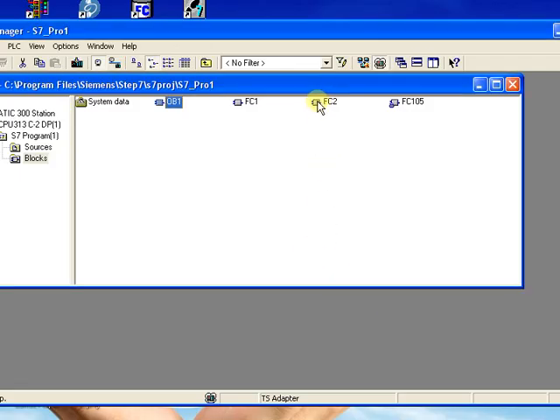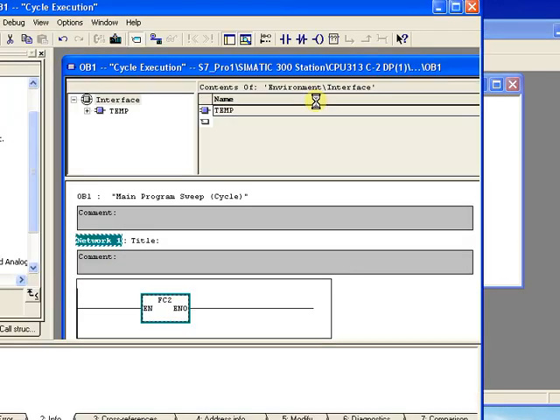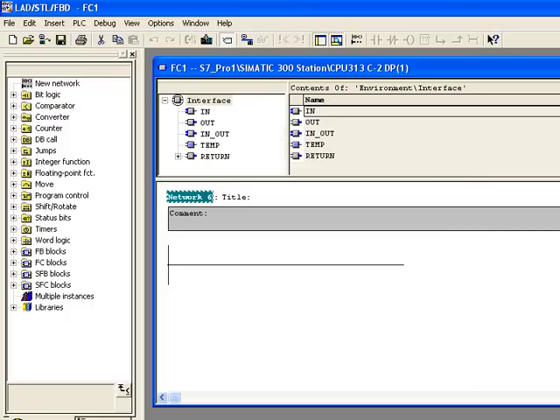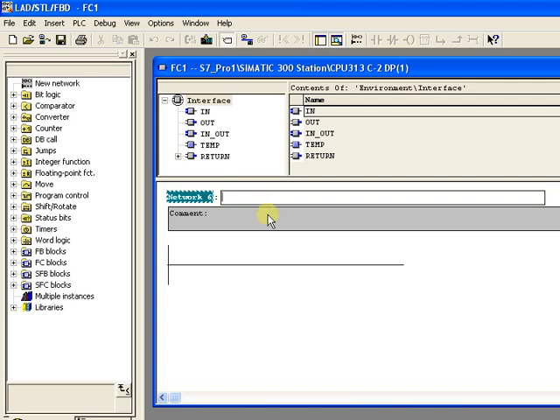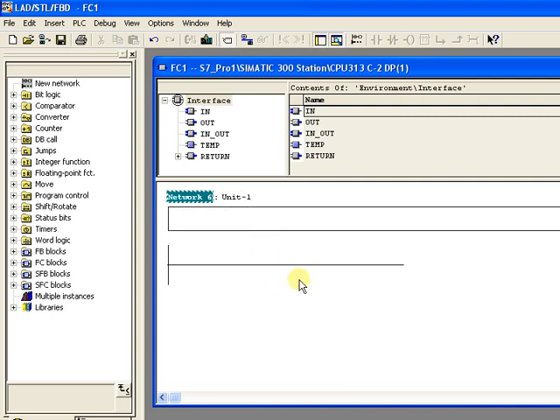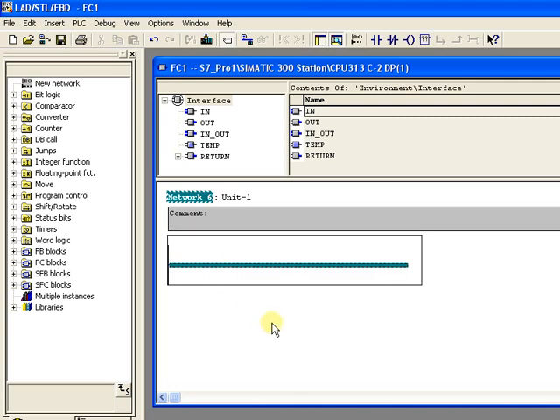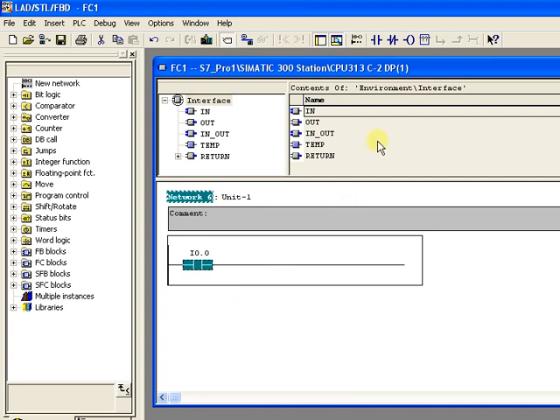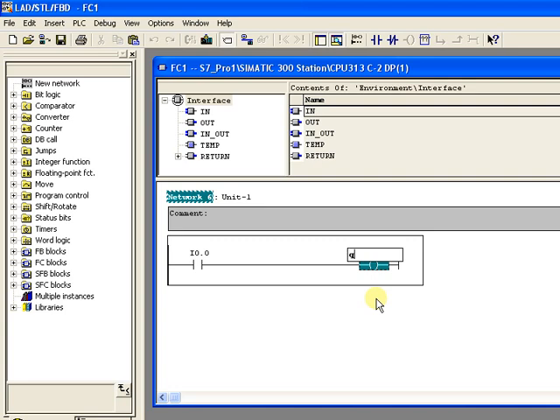Now click the function block to start programming. Click on the network title and you can add a title like 'Unit 1'. You can also add a comment if you want. Then click on the power rail and click a normally open contact — that means input — and give it the address I 0.0. Then add a relay coil with address Q 0.0.